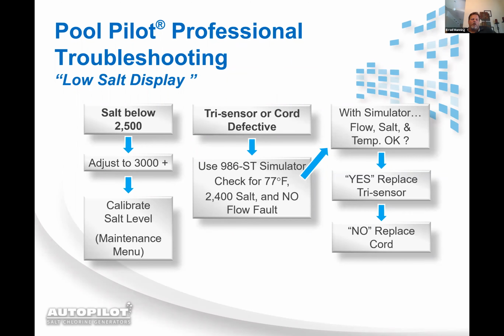Now, unlike flow, when you plug the simulator in for a flow message, flow is almost instantaneous. Within a couple seconds, if there's not a problem with the power supply, that flow message will go away. Salt, however, is a resistance read, so it takes about a minute to a minute and a half for the system to acclimate itself to the simulator.